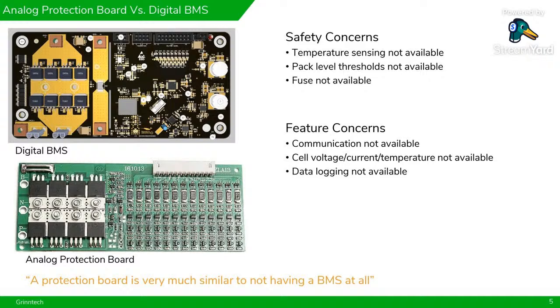As I said, temperature sensors are not available, and pack level thresholds aren't applicable because these bottom BMS units only work at cell level - nothing is calculated or acted upon at the pack level. Fuses are also not part of the BMS, though you can add one externally if you want. I've seen very often that there's no fuse in these batteries, but that's a design decision. Ultimately, comparing the percentage of features in these protection boards versus a proper digital BMS...